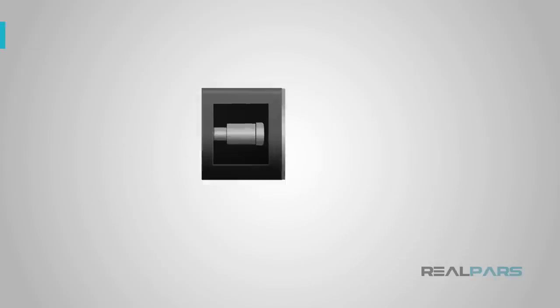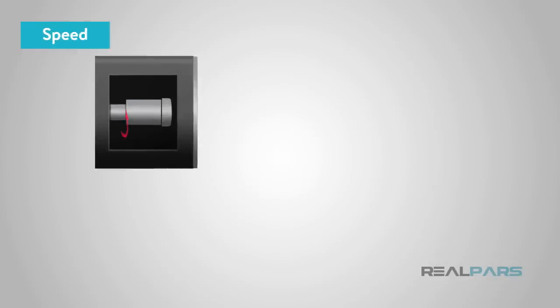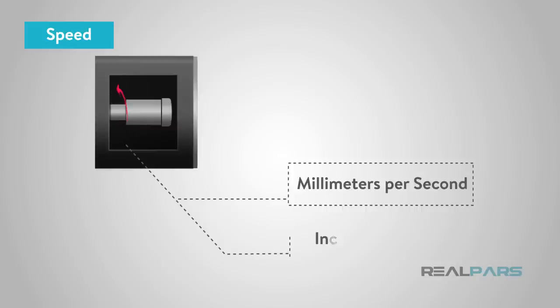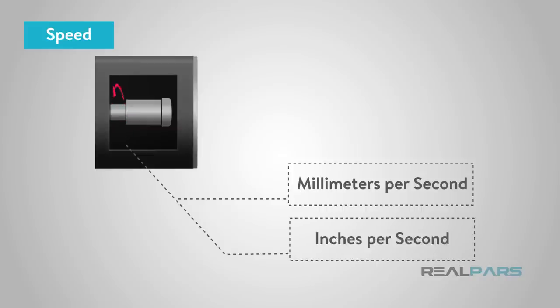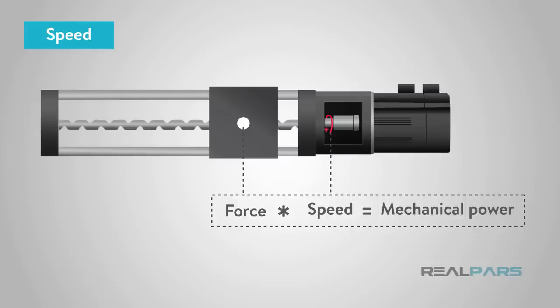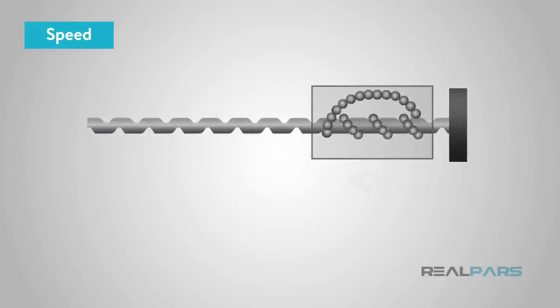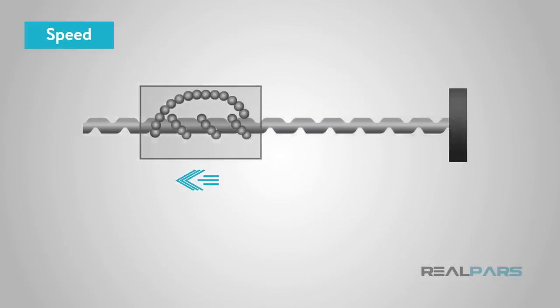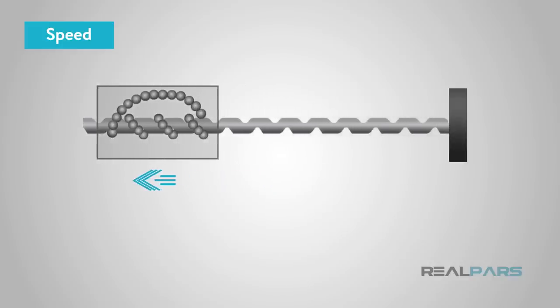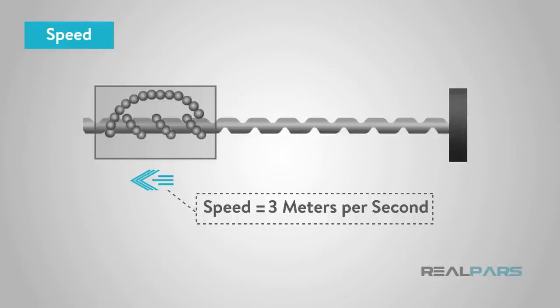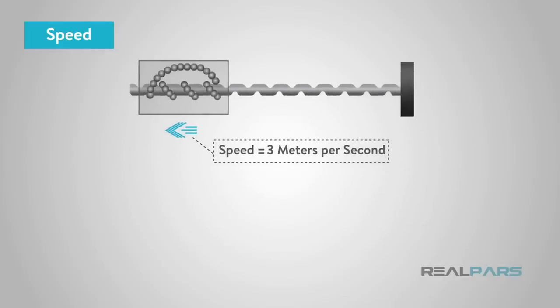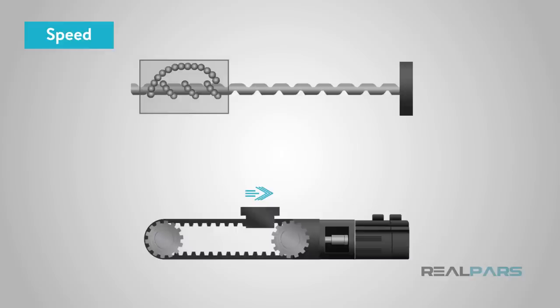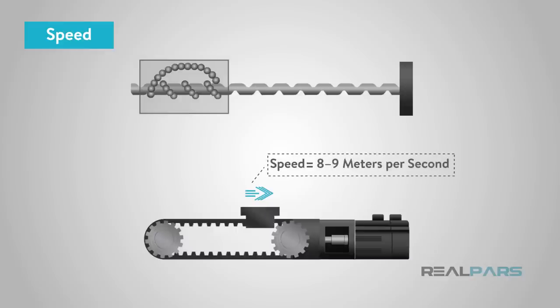Next, you'll need to determine the speed on how fast in millimeters per second or inches per second the actuator will need to move. Determining the speed combined with the force will give you the mechanical power required and how powerful the motor must be. Traverse speeds and traverse times are somewhat limited with ball screw drives. Ball screw actuators typically have a maximum speed of 3 meters per second and for belt drive actuators, the maximum speed is around 8 to 9 meters per second.